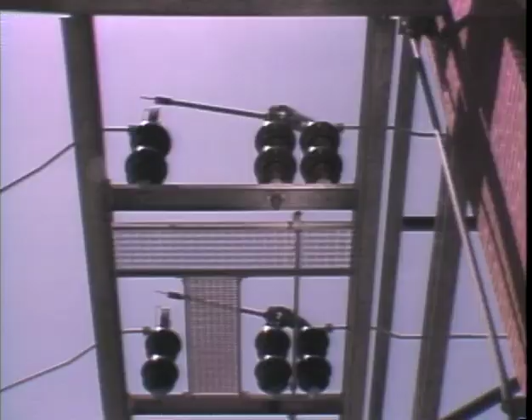Disconnect switches are used primarily to isolate a circuit from its power supply once the circuit has been de-energized. Isolating is a secondary protective measure. It creates a visible break in a circuit so that if the circuit breaker is closed accidentally, the circuit remains de-energized.